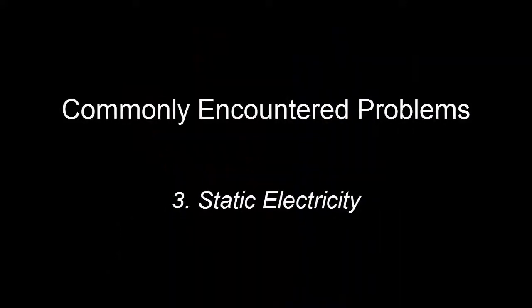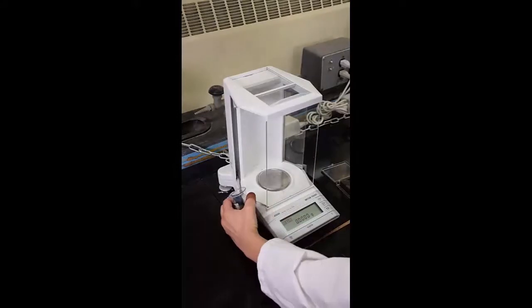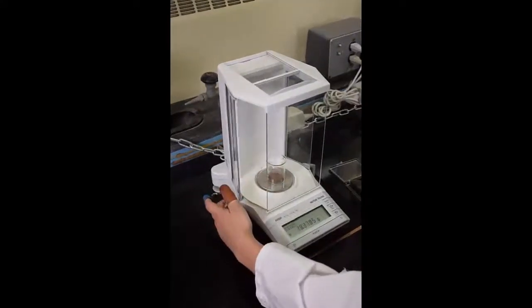3. Static Electricity. A buildup of static electricity on the surfaces of the balance compartment and on the container being weighed may cause erratic balance readings.